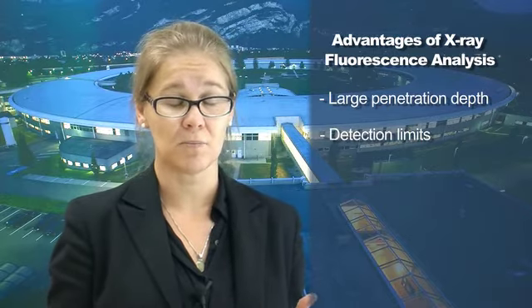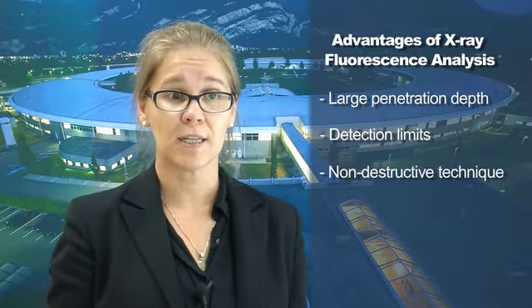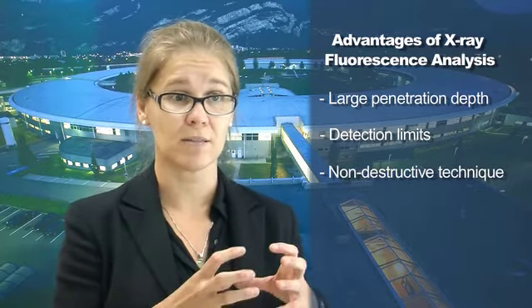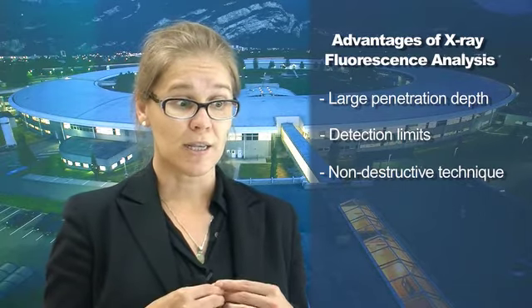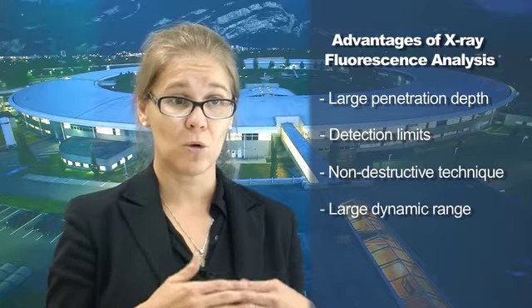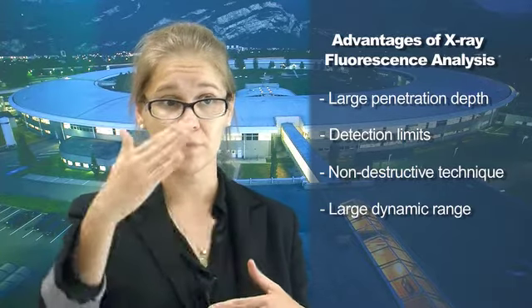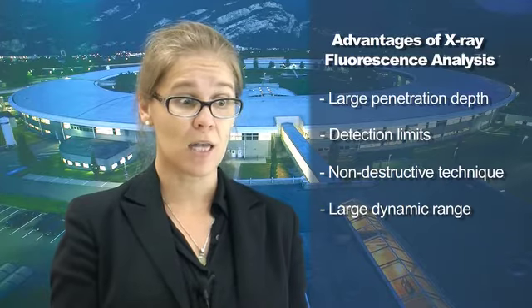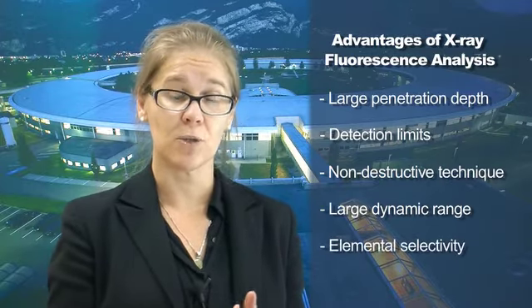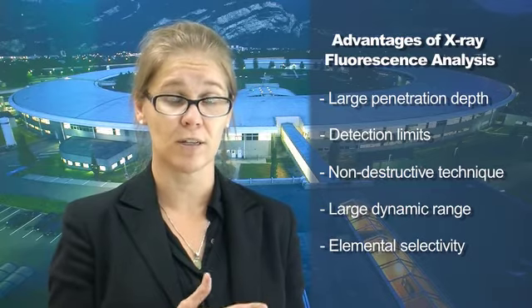X-ray fluorescent analysis compared to electron or particle-induced techniques has plenty of advantages. One is the large penetration depth, which gives more than surface sensitivity. The second is detection limits that can reach PPB levels. It is non-destructive — we don't need to section the sample, so you can bring it as-grown. We also have a large dynamic range, going from PPB to 100%, covering the full range of intensities.